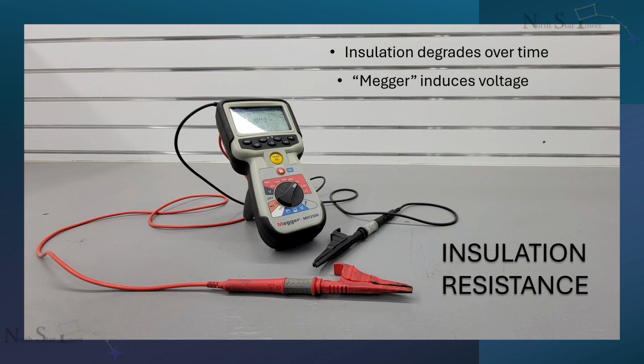The Megger measures how much current leaks through the insulation. High resistance means the insulation is intact. Low resistance means contamination, aging, or internal damage. Degraded insulation is a silent threat. It can cause current to arc out of place, leading to equipment failure, injury, or worse, and it often goes unnoticed until a breakdown has occurred.